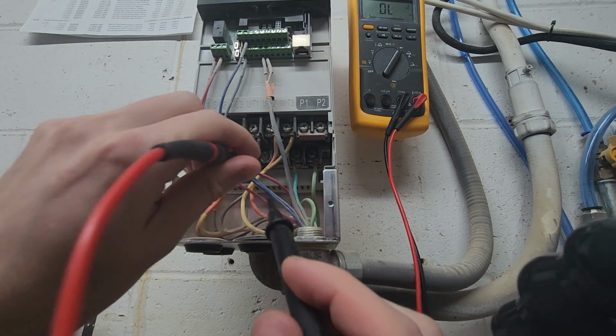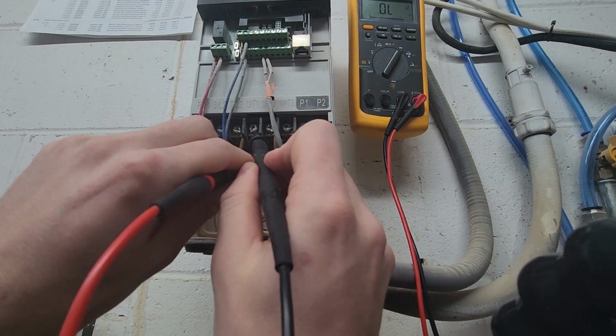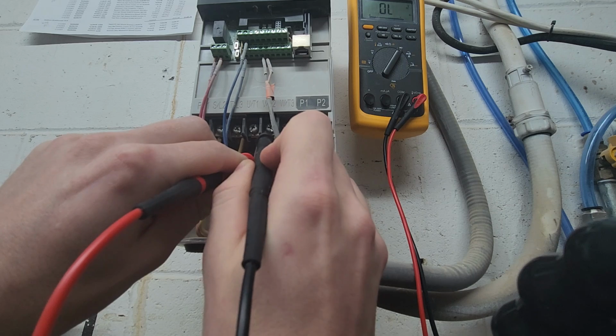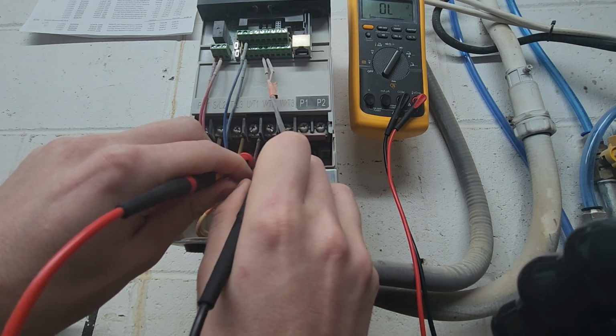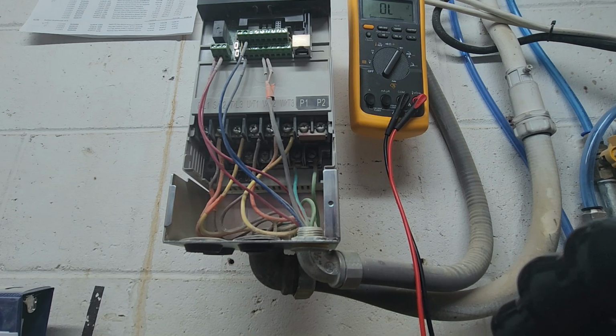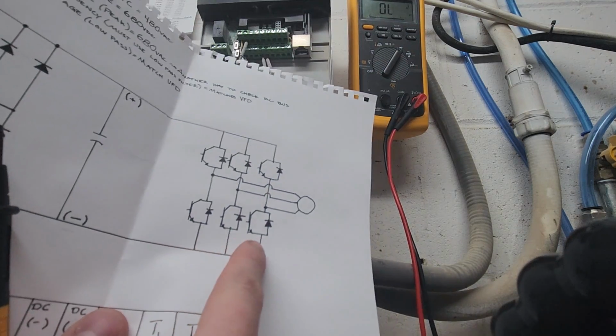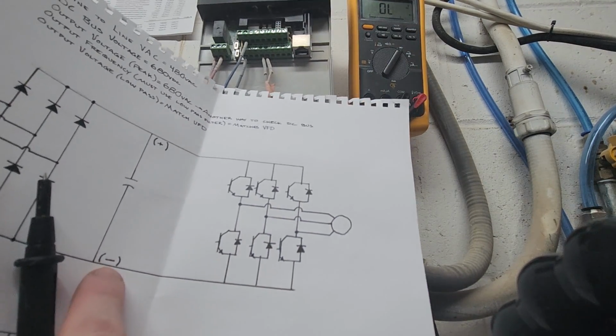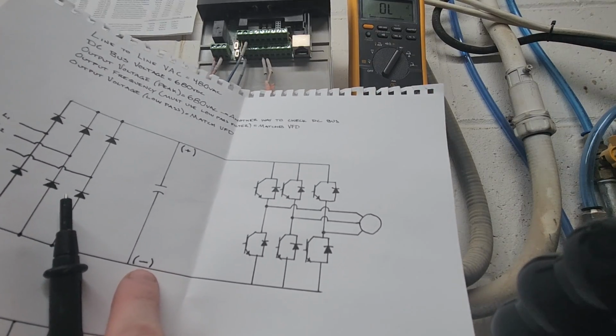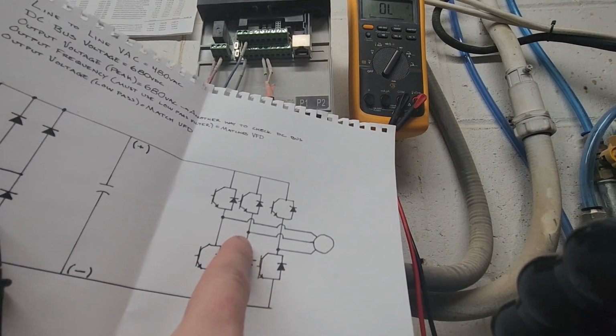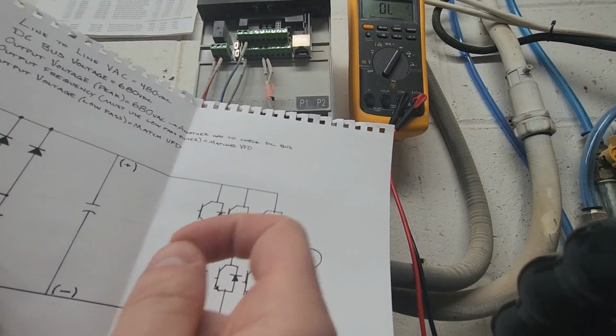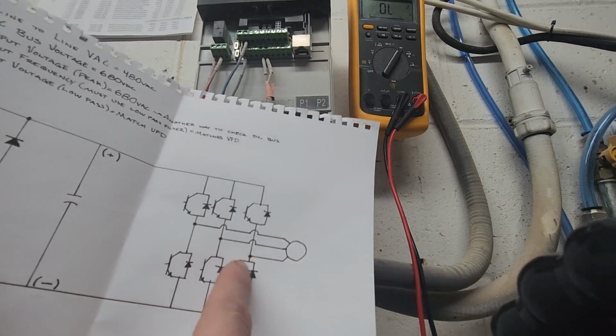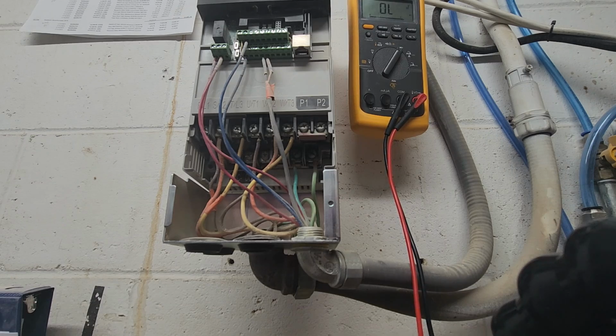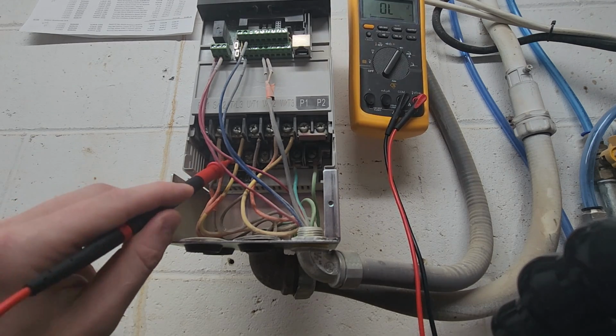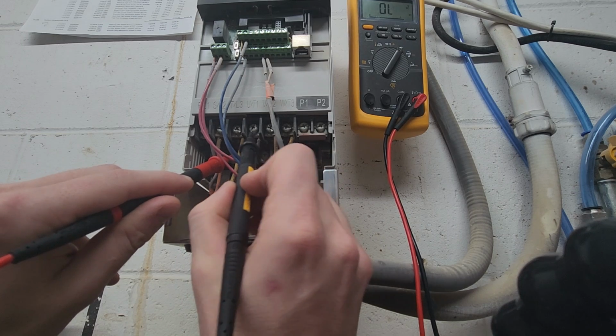Now we'll flip this around. Positive on your DC bus positive, negative on your outputs. Over limit, over limit, over limit. That's perfect. Now we will check our bottom 3 diodes. So we'll put our positive probe on DC bus negative, and our negative probe on the outputs.